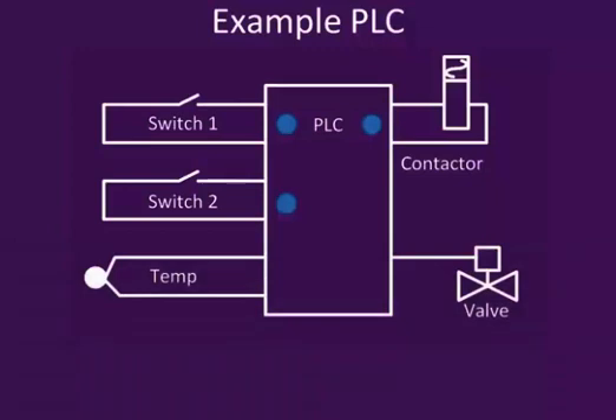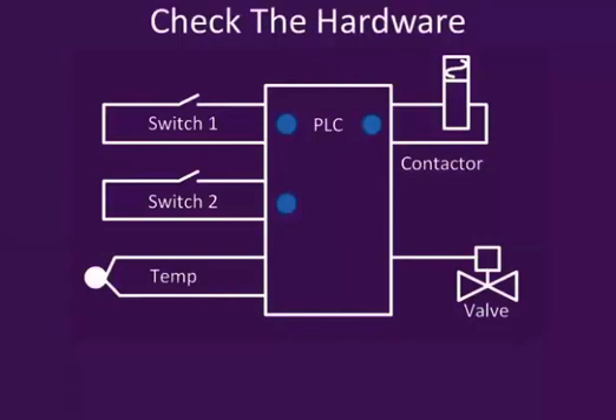I'll take a simple system and go through the different ways and the different stages of commissioning. The first stage is to check the wiring. You could do a 100% point-to-point checking, where you check that each core is connected to the correct place using some sort of continuity check. To do this, you disconnect one end from the PLC and check continuity to the switch. Then you disconnect the other end from the PLC and check continuity to the other side of the switch.